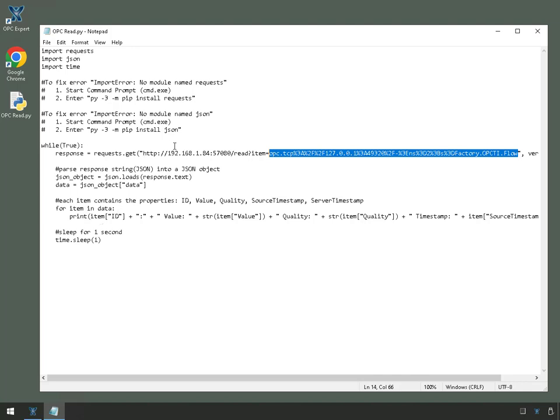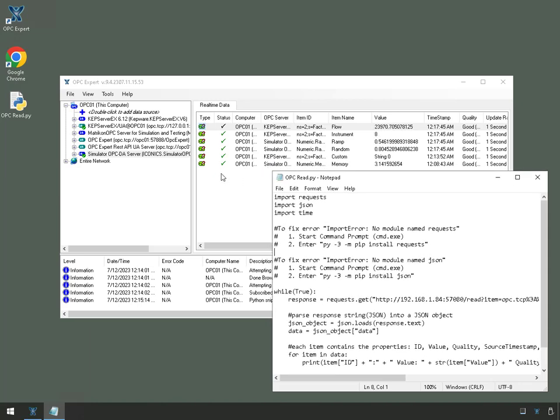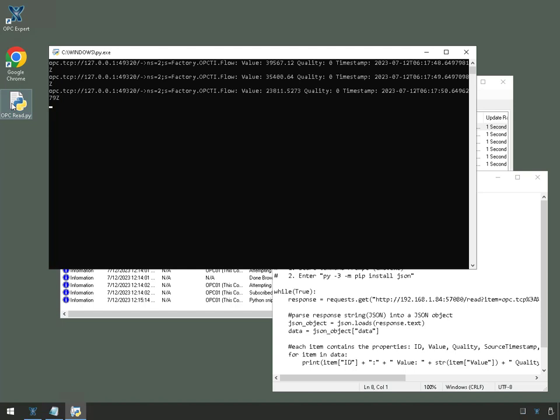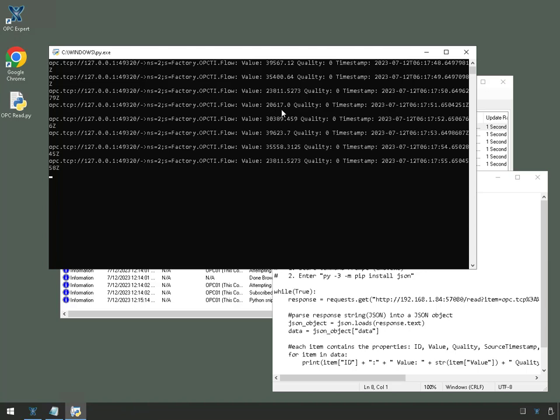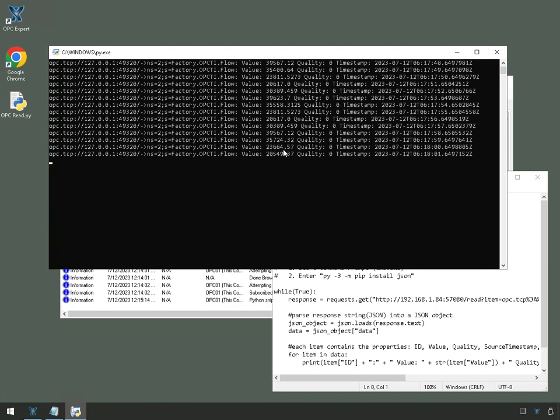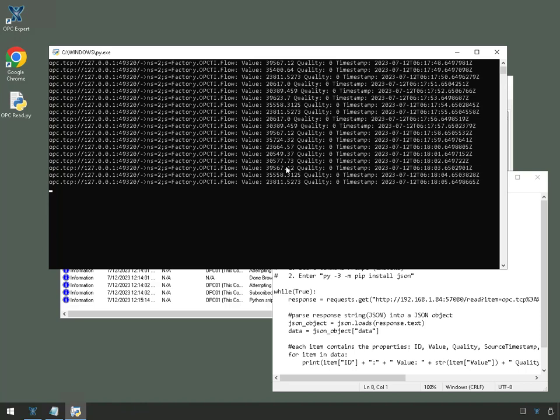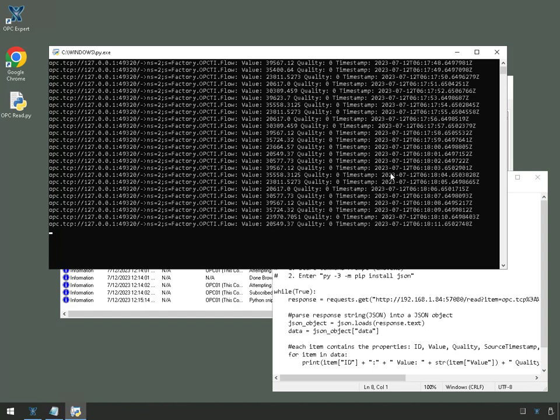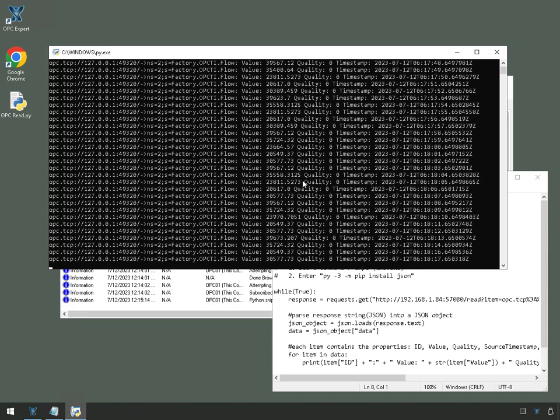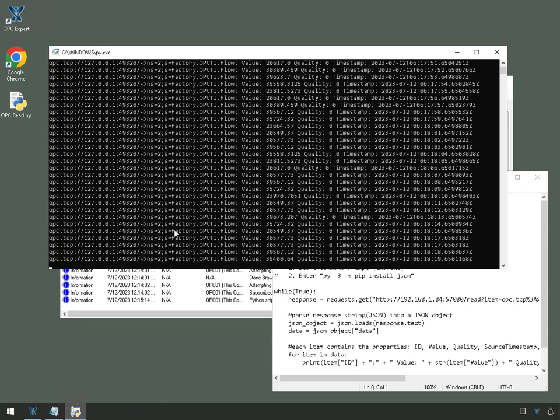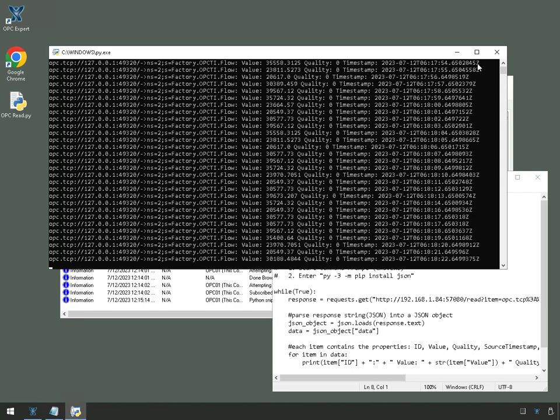This is actually already saved. Watch this, I'll just run this, double click it, and we can see the values. Here's the value right here. I'll make this a little bit wider. There we go, it's a little bit easier and you can see that every second we keep getting new values. You can see the quality in OPC UA, quality of zero actually means it's good, the timestamp and you can see this is in UTC. There is the actual item ID and you can see where it comes from.